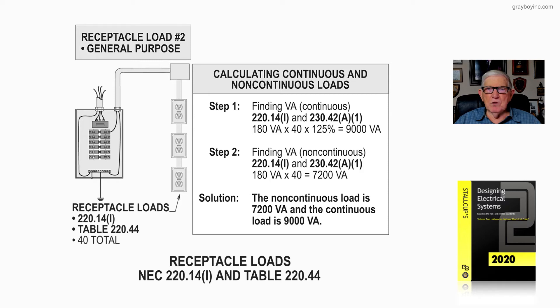In step one, we're going to figure the continuous load. In the title heading, we're calculating the non-continuous and the continuous load under 220.14(I) and 230.42(A)(1). If they're continuous, it would be 180 VA per outlet times 40 times 125%, giving 9,000 VA as the continuous load.